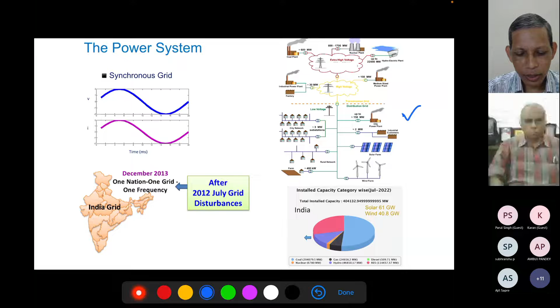This September, in an event in Netherlands, the corresponding protection system failed, and it failed for 50 seconds, not milliseconds or a second, 50 seconds or more. The corresponding greater than 100 kV system line, having the fault current significantly, you will see the line start melting and going down onto a railway supply system, and then short circuit happens and fire continues.